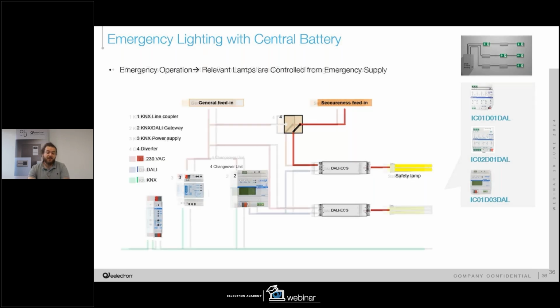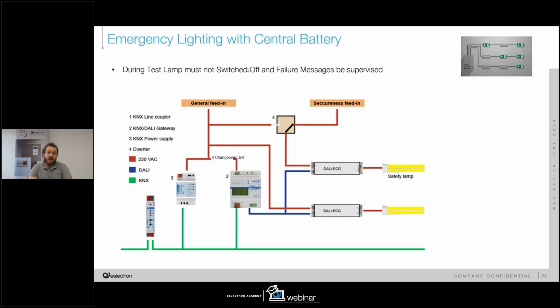In addition, something that is very important: when you run a test using a BMS to test the central battery, we have to take care of what is happening. I mean, during this scenario, we can see how the DALI gateway is powered on, meaning that it is alive and can control the status of the ballast. But if we enable the secure test, there will be a relay that will cut off also the DALI bus. So there will be no more communication between ballast and the DALI bus.